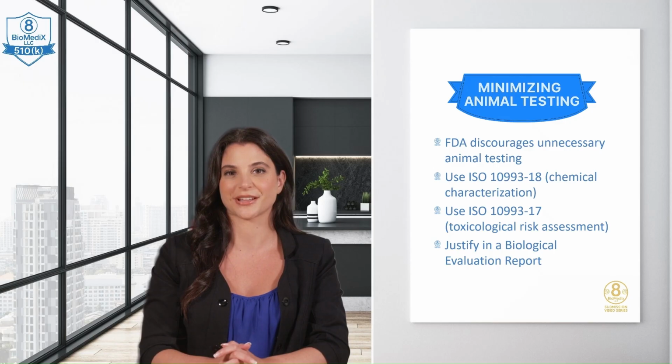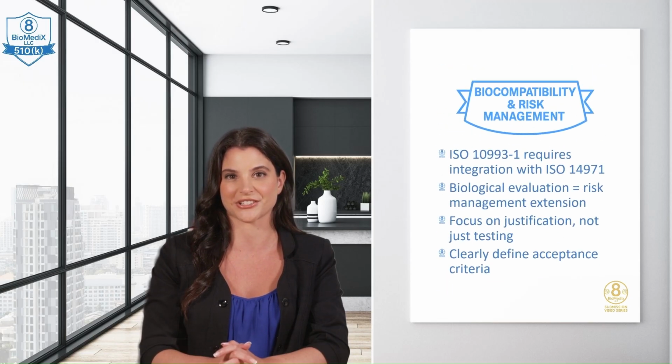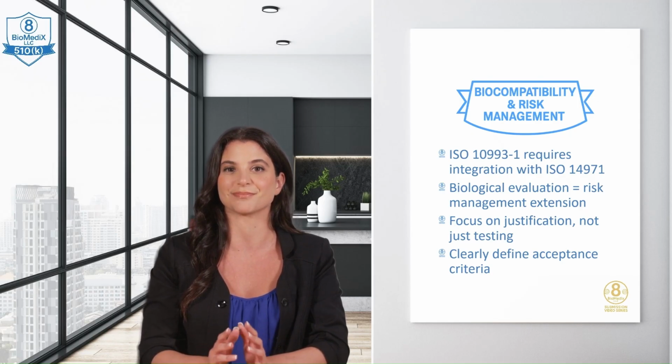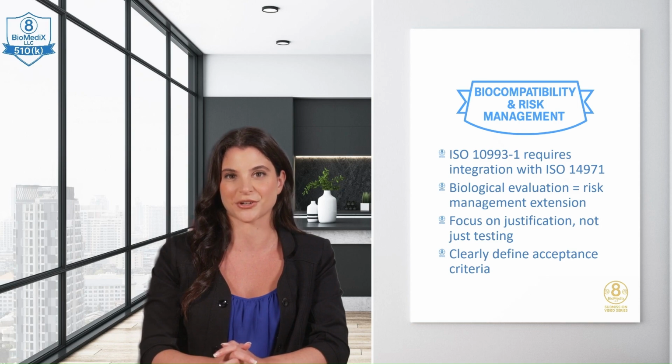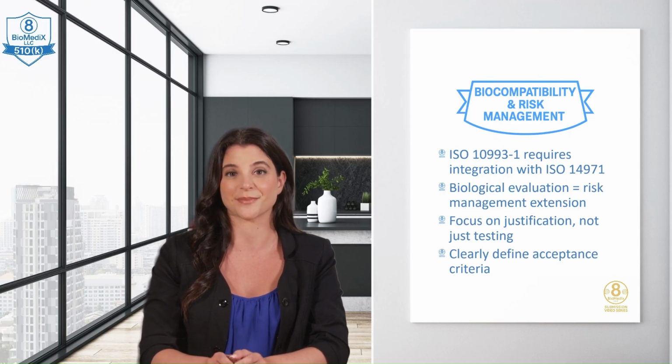Biocompatibility and risk management. This is where ISO 14971 and ISO 10993-1 intersect. The standard explicitly states, biological evaluations must be conducted within a risk management process. So, your biological evaluation is essentially an extension of your risk management plan. It's not just about testing, it's about justification. What are the risks? What data addresses them?